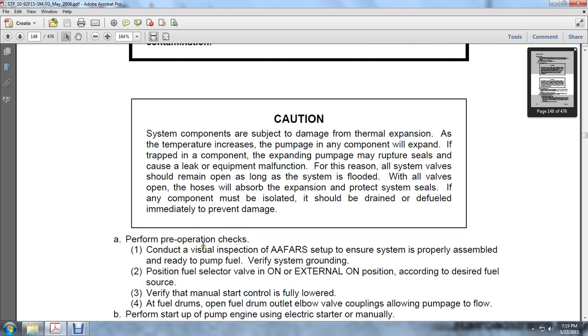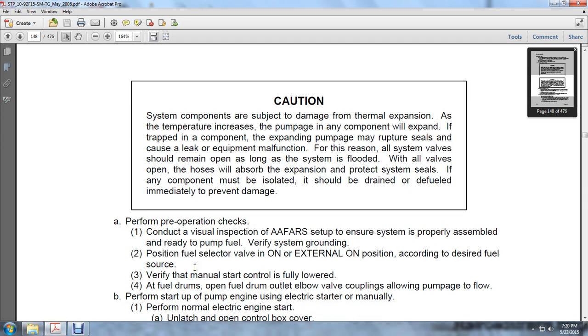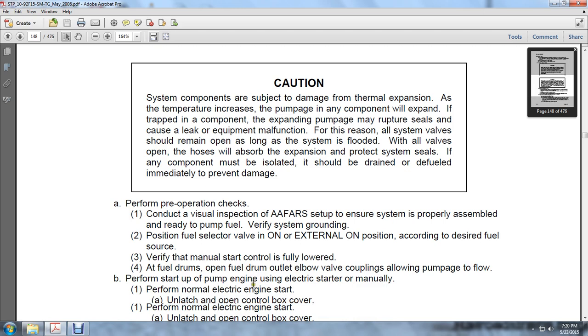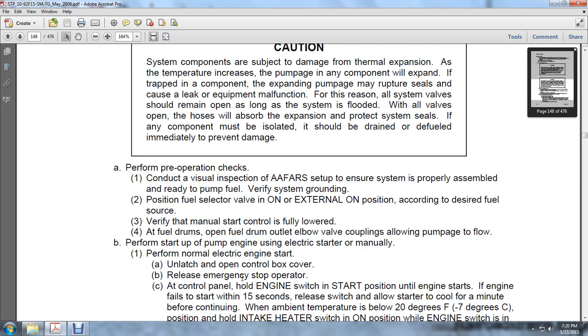Before performing operation checks, conduct a visual inspection of the advanced aviation forward area refueling system set up to ensure the system is properly assembled and ready to be fueled. Verify the system grounding. Position the fuel selector valve to the external on position according to the desired fuel source. Verify the manual start control is fully lowered. At the fuel drums, open the fuel drum outlet elbow valve. The couplings allow pumpage to flow. Perform the start of the pumping engine using the electric start or manually.